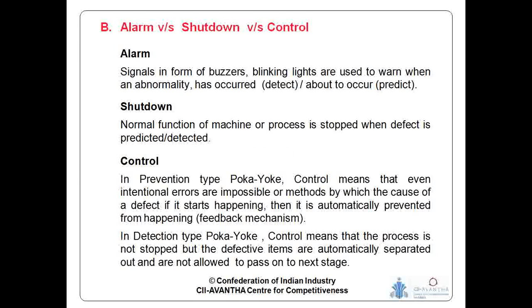Suppose a conveyor, I'll take a classic example. There was a company where the motor of the conveyor used to burn once every month. The reason was the conveyor would get stuck somewhere, and the person wasn't able to understand that it was stuck, so the motor with respect to the gearbox kept running continuously, putting a lot of load onto the motor, and the entire motor used to burn out. So the sensor they provided was an overload sensor with respect to the motor. Whenever there is overload on the motor beyond a certain limit, the entire system will shut down. So I had saved my conveyor from breaking, and saved my motor from burning.